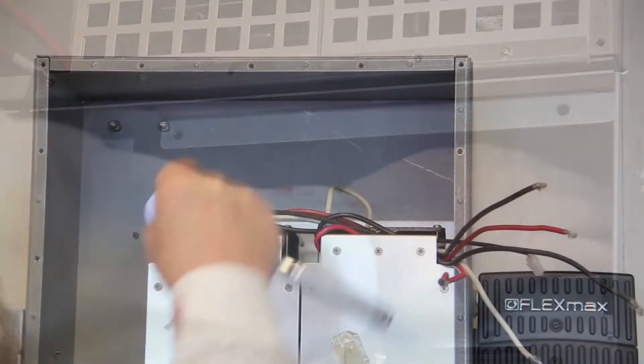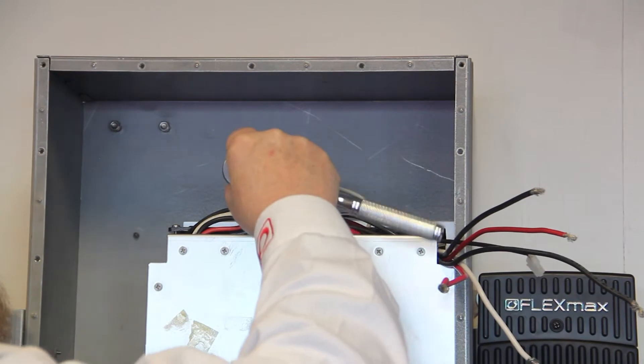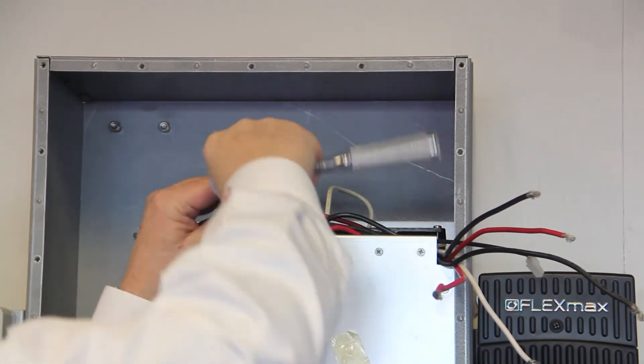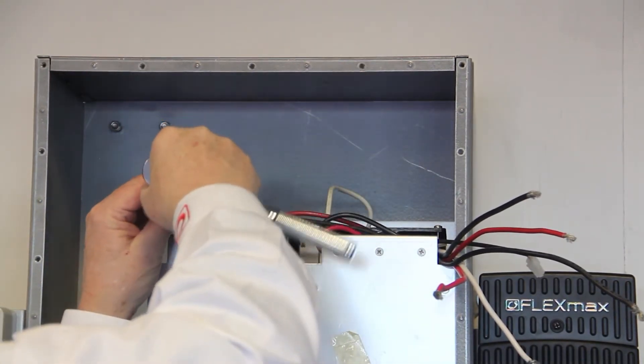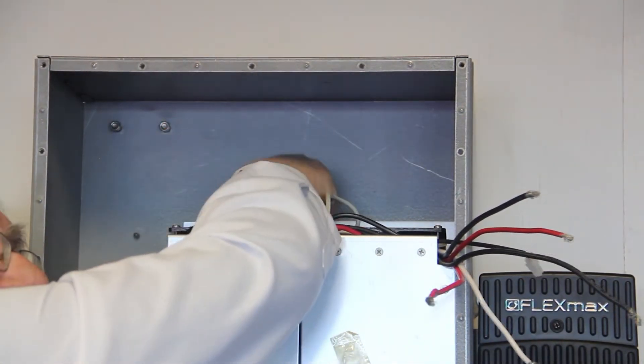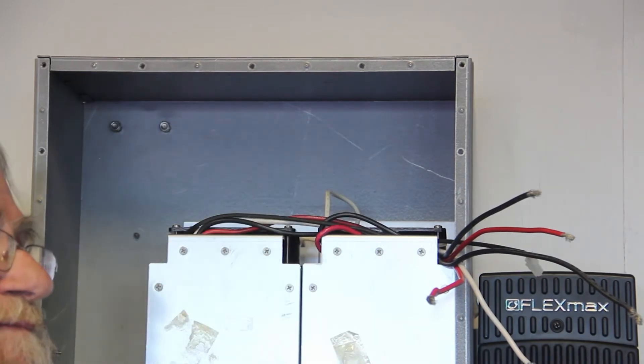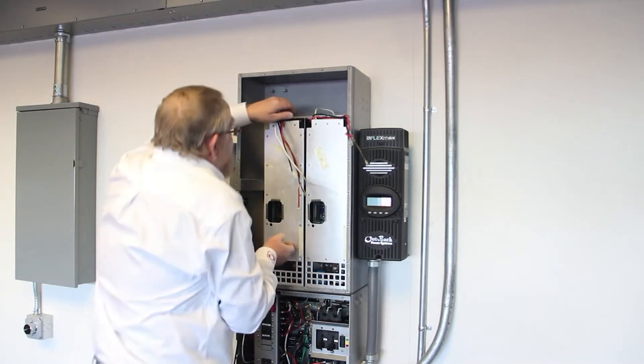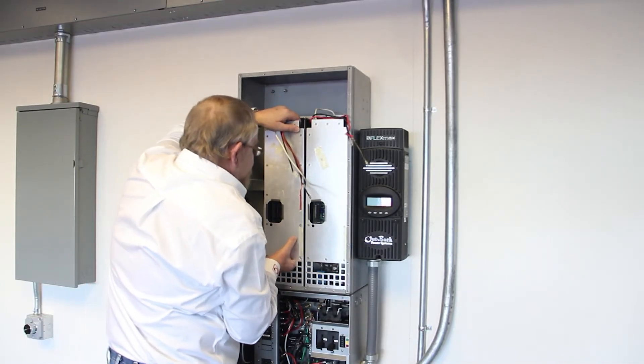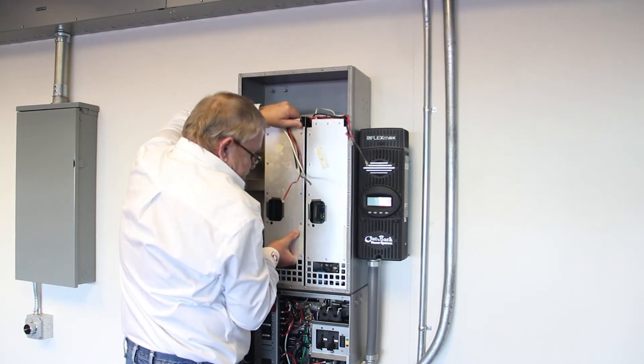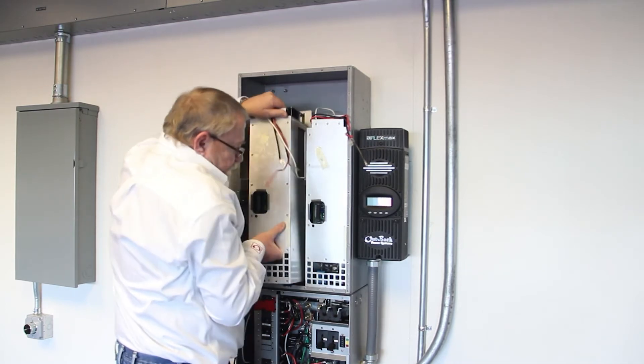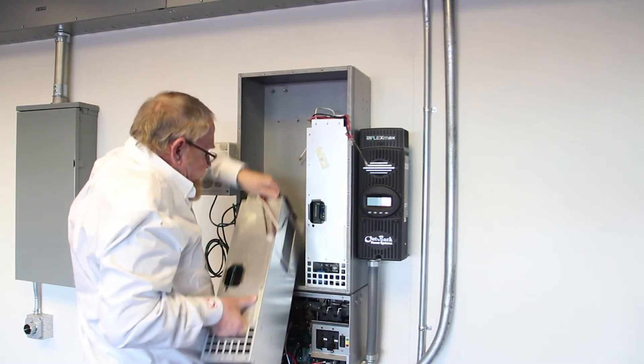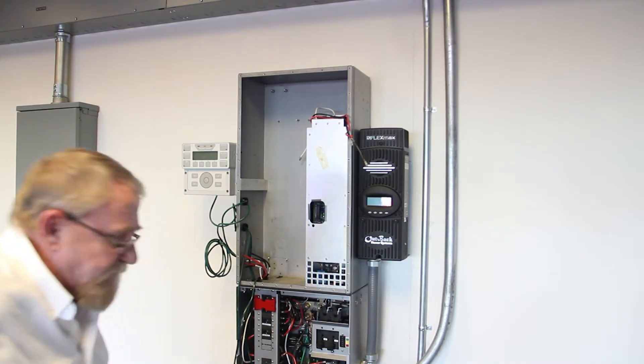Remove the two upper nuts from each power module located above the fan using a socket wrench with a 10mm socket. Using the two handholds provided on the power module, lift up at least one inch and then outward to remove the power module.